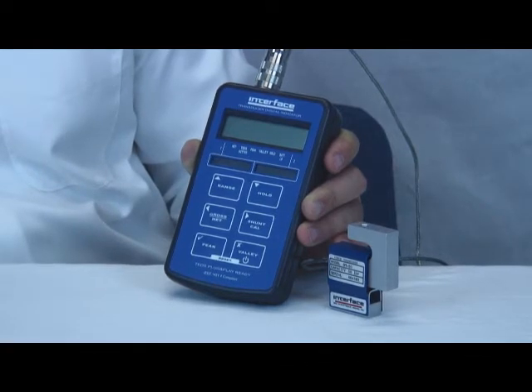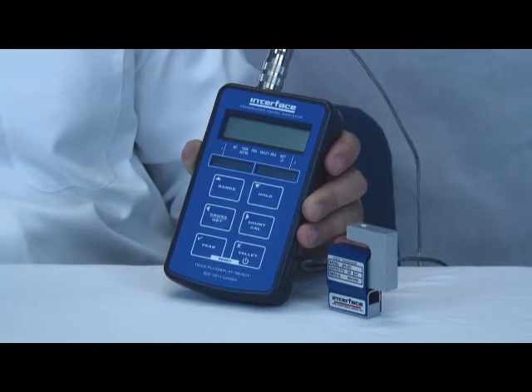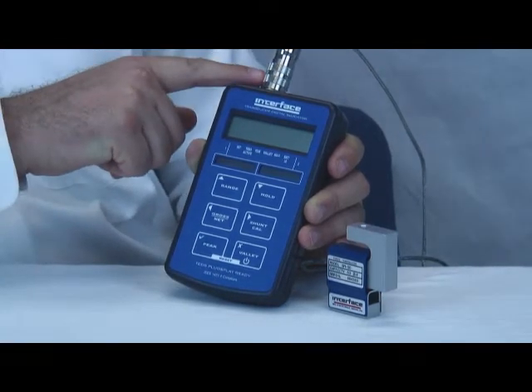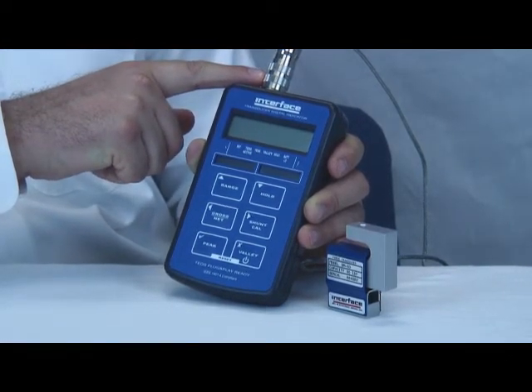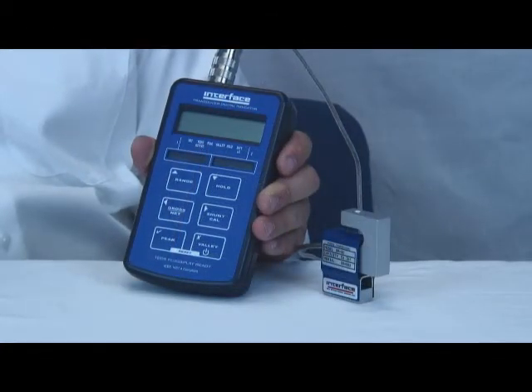Otherwise, it will be necessary to calibrate the 9320 with your chosen sensor. If purchased separately, you may have to install the included mating connector on the end of your load cell. The 9320 can be calibrated either by applying a known load or by using the millivolt per volt value from the load cell calibration certificate.